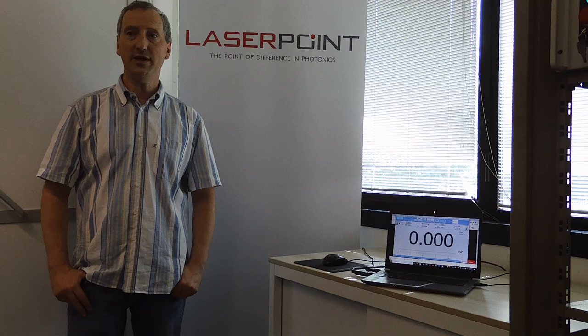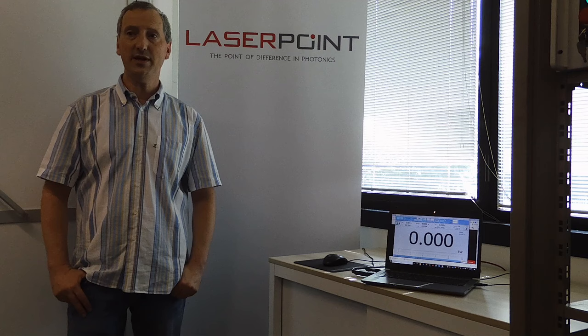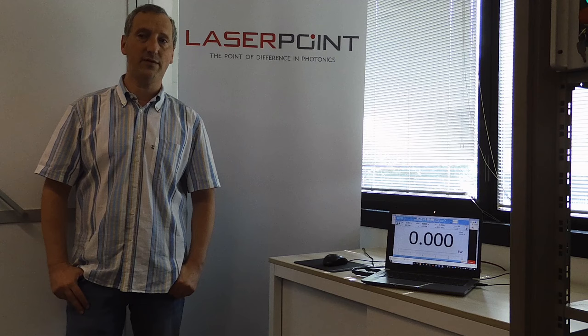Our calorimeter is a very compact solution to accurately measure very high powers, up to 12 kilowatts. Useful during installation and then for service and maintenance of multi-kilowatt laser sources.